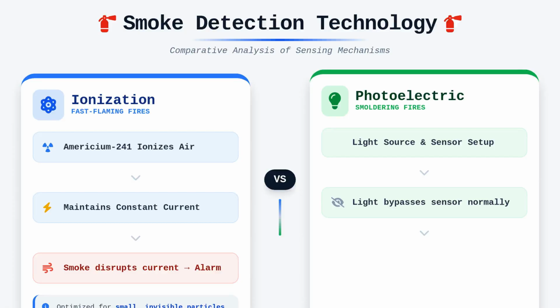Conversely, photoelectric detectors utilize a light source and a photosensitive sensor arranged so that light does not normally strike the sensor. When smoke enters the chamber, light scatters off the particles and onto the sensor, which then initiates an alarm signal. This technology is inherently better at detecting larger, visible particles produced by smoldering fires, making it a critical component in balanced protection strategies.